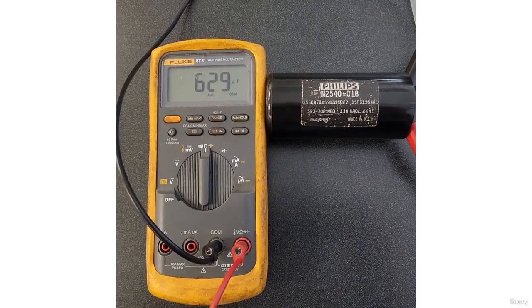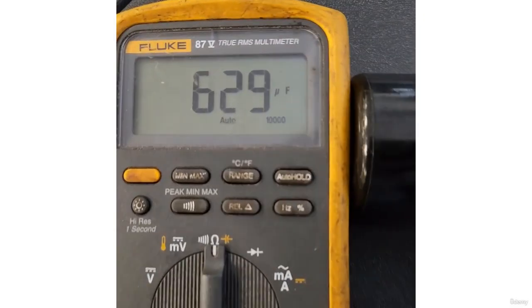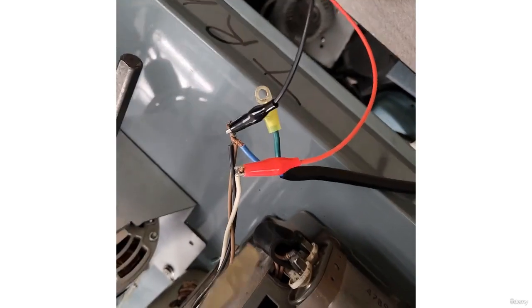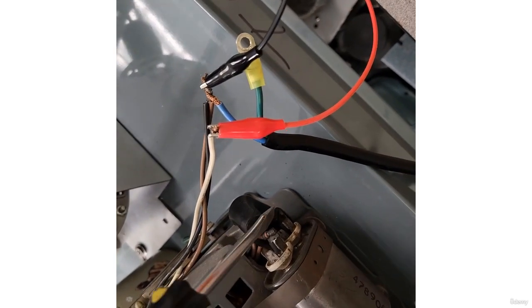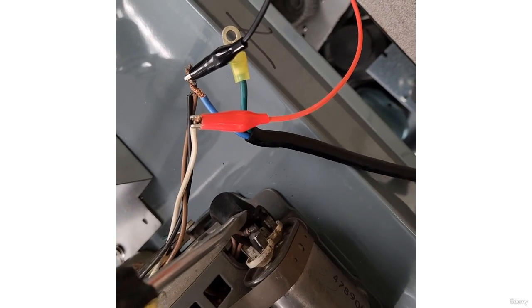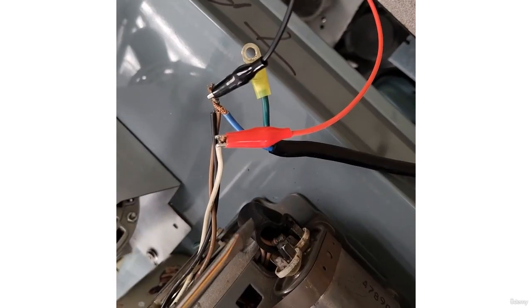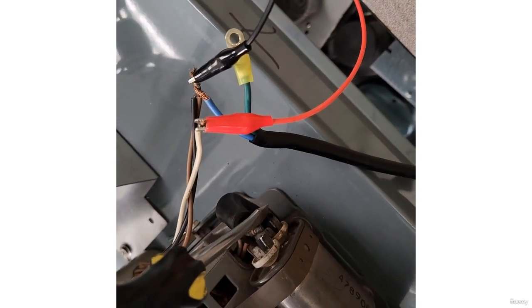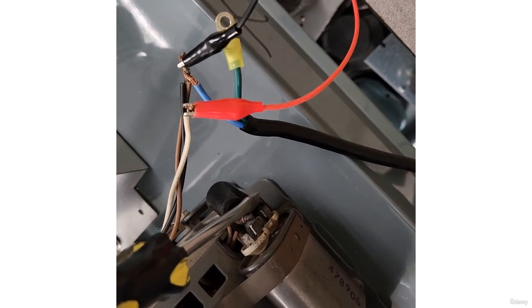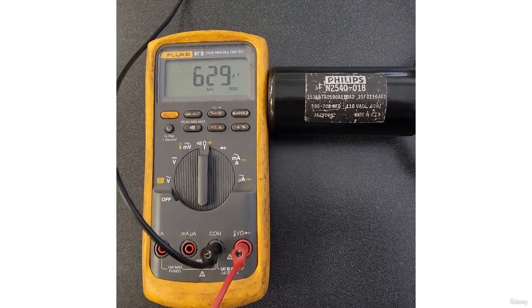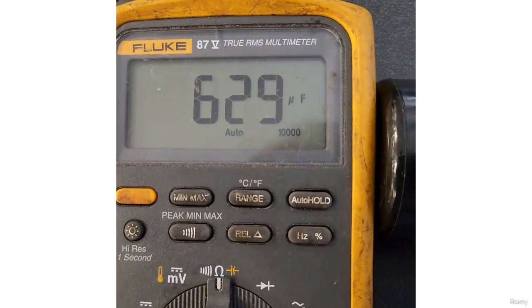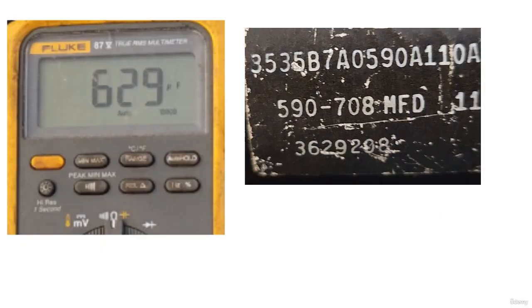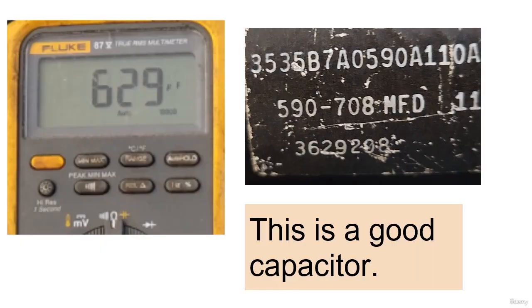To test a capacitor, take it out of the circuit and use your meter set on microfarads. Always discharge a capacitor before putting your hands on the terminals. You can do this by placing a screwdriver across the terminals. Be careful, sometimes it will put off a large spark. Test across the terminals and you should be within 10% of that rating. If you are within 10%, your capacitor is good.